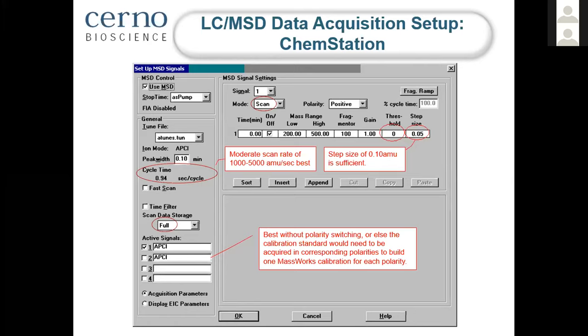And then you need to build a polarity appropriate calibration for the analysis, which means in the positive mode, you need to build a positive mode calibration. In the negative mode, you need to build a negative mode calibration to apply to the corresponding mode of the sample unknown analysis. It can be done, but you do have to separate out the positive mode and the negative mode. MassWorks software is capable of doing that, but we suggest that you start with a single polarity to get familiarized first.